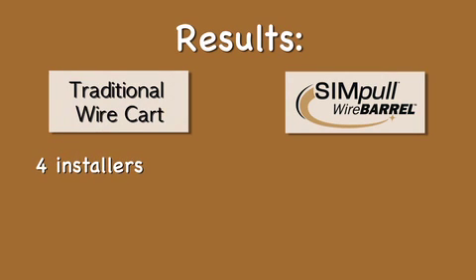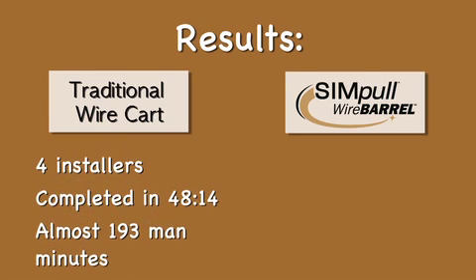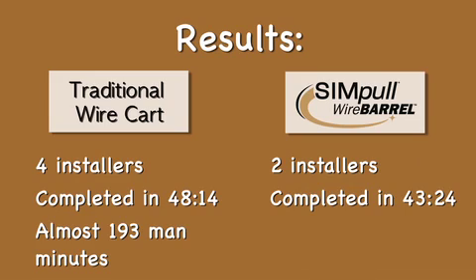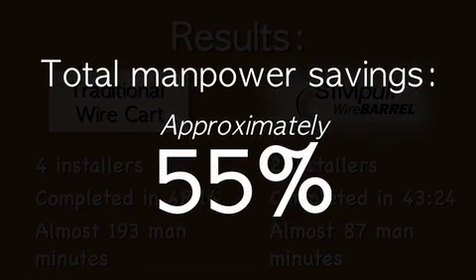The results of the third comparison show that four installers using the traditional wire cart method completed their pull in 48 minutes 14 seconds, a total of almost 193 man minutes. Two installers using the SIMpull WireBARREL completed their pulls in 43 minutes 24 seconds, or an equivalency of almost 87 total man minutes, resulting in a total manpower savings of approximately 55%.